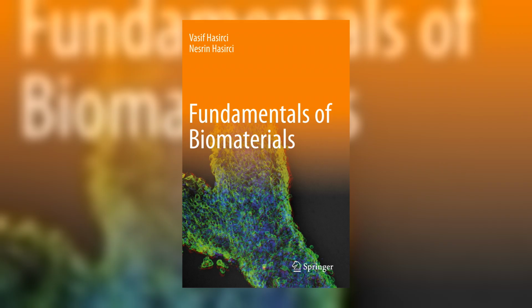The generative move is to partition the failure space by mechanism. Enumerate the distinct ways blood destroys itself on contact, then assign a probe to each, because a surface can be inert to coagulation yet still ignite complement. Compatibility is a checklist over orthogonal catastrophes rather than a property of the material. The standard's 5 categories are exactly that partition.